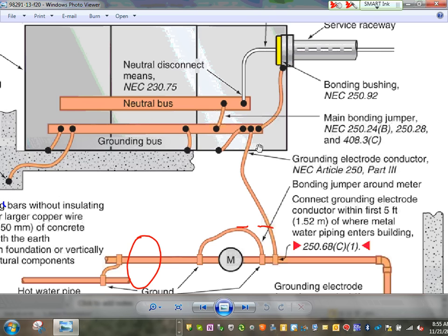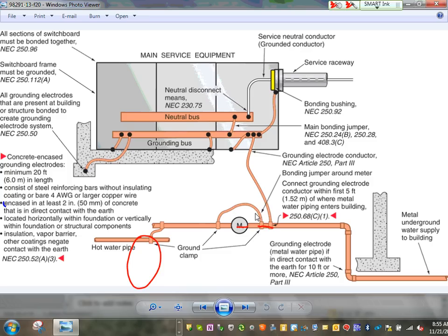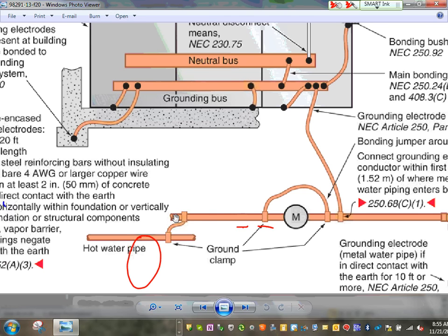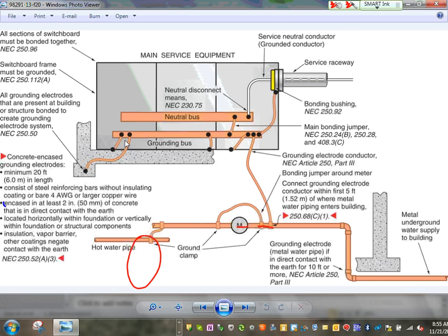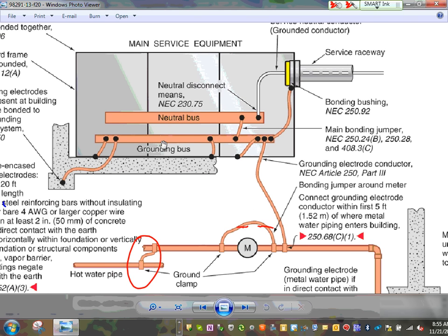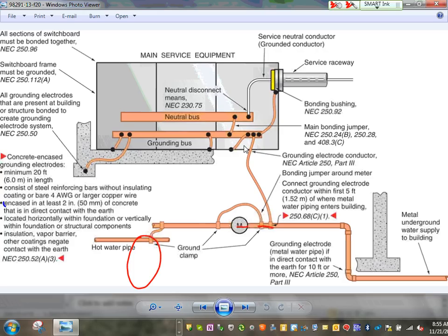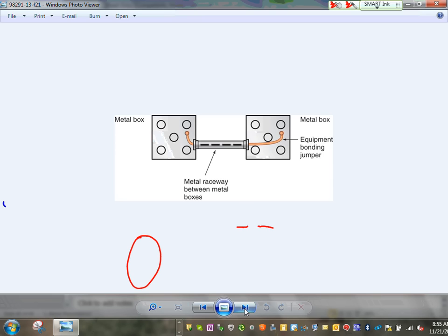So when you bring your grounding electrode conductor to the water pipe, you have to bond across the meter so the utilities can maintain their meter. You have to bond to the hot water. Can you see the hot water pipe has to be bonded? So all of it is at the same potential. You bond to the concrete-encased electrodes. Here's my neutral inside the switchgear. Here's my bar. You bond the neutral to the ground. You bond the conduit coming in. And again, I promise you guys, you will hear about grounding and bonding in the spring more than you can even imagine. I go through this in detail with my sheets.